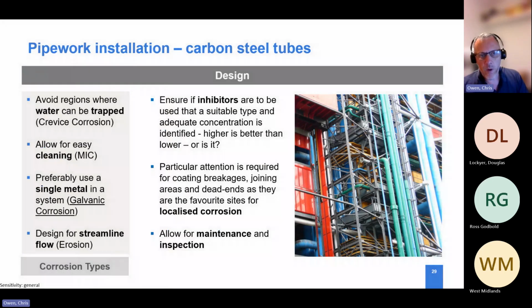When we talk about pipework and specifications, it's important to identify exactly where the pipework is being used and what issues need to be taken into consideration. We're talking about corrosion. Carbon steel does corrode, however it can be exposed to a variety of different application environments, and as long as those environments are understood, the risks can be easily mitigated. What I'm going to do is go through the various different corrosion mechanisms.